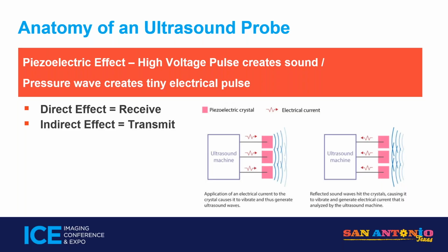We have the direct effect, which is really the receive function. The receive function in ultrasound is where the sound wave strikes the probe, causing it to generate tiny electrical pulses. So that's what we call the direct effect, okay? The indirect effect is where we hook up high voltage to the crystals and cause them to send a sound wave into the human body, okay? So just some physics. We don't get into the math.